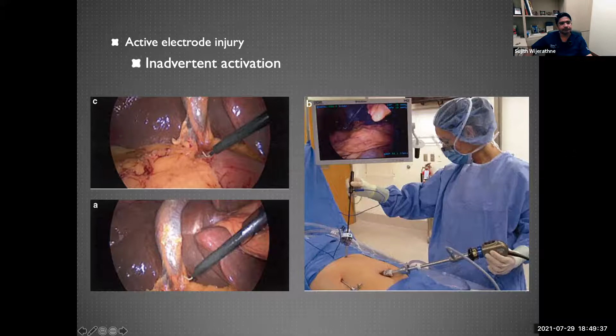Over to you, Sujit. Thanks. To conclude this part, we need to talk about active electrode site injury. Sometimes during a procedure we are not looking at where our active electrode is, and there's a chance we may accidentally press either the coagulation or cut mode with the foot pedal without looking at where the active electrode is touching. This is where inadvertent activation can happen, which can result in tissue injury - this has to be kept in mind.